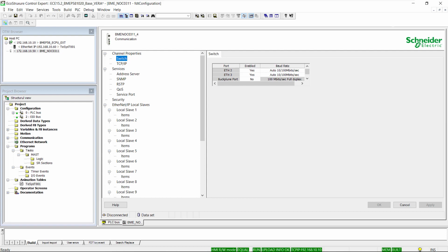However, if we use the explicit communication function blocks within the PLC logic, it will be able to access this information, then make it available as PLC registers that can be accessed by the SCADA system through the data dictionary or localized memory words.